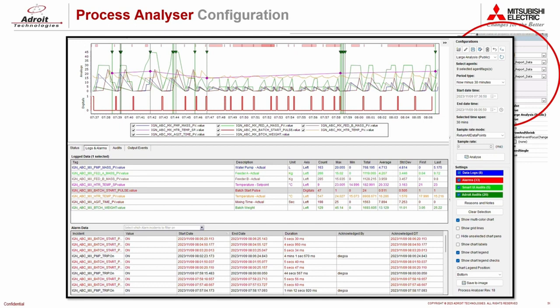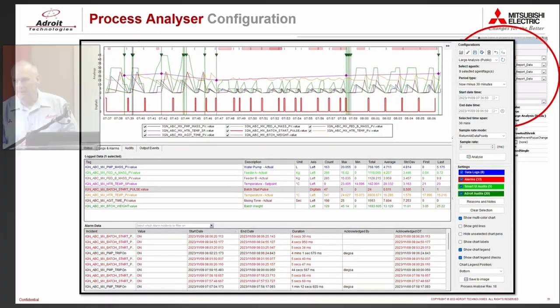So it amalgamates the log data, the event data when things happened in time, with alarm data at the top there, so you can see when things went into alarm, with digital data for status down here. So a motor turned on then, an alarm turned on then, the process is running then, etc. And then you can filter out things very quickly to try and understand and hone in on what the problem is.